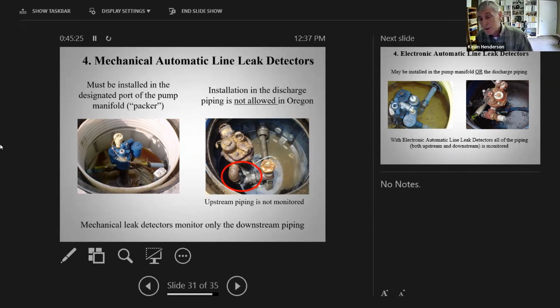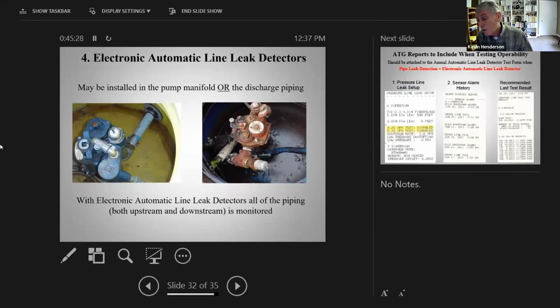If you have a scenario where, for some reason, you cannot put the T in the immediate discharge, then you can just do electronic leak detectors. Of course, you could replace the pump itself, but electronic leak detectors can be put anywhere in the pipe, and it does not matter if it's upstream or downstream of the submersible or the leak detector. The electronic leak detector is going to be able to monitor the entire pipe, both upstream and downstream. So in that case, it does not really matter where the electronic leak detector is.